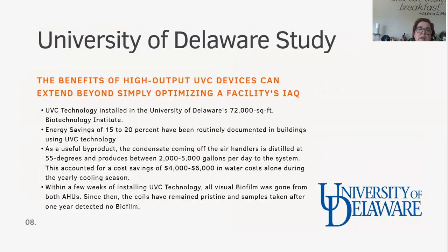In the University of Delaware, they were looking at how to save money with respect to makeup water. They installed UVC in a 72,000 square foot biotech building, looking for energy savings and water savings, and they were able to document 15 to 20% energy savings in the buildings by using UVC. They also had a byproduct they really had a use for: condensate coming off of the air handlers was distilled at 55 degrees, and it produced 2,000 to 5,000 gallons per day. That saved them between $4,000 and $6,000 in water costs alone during the yearly cooling season.